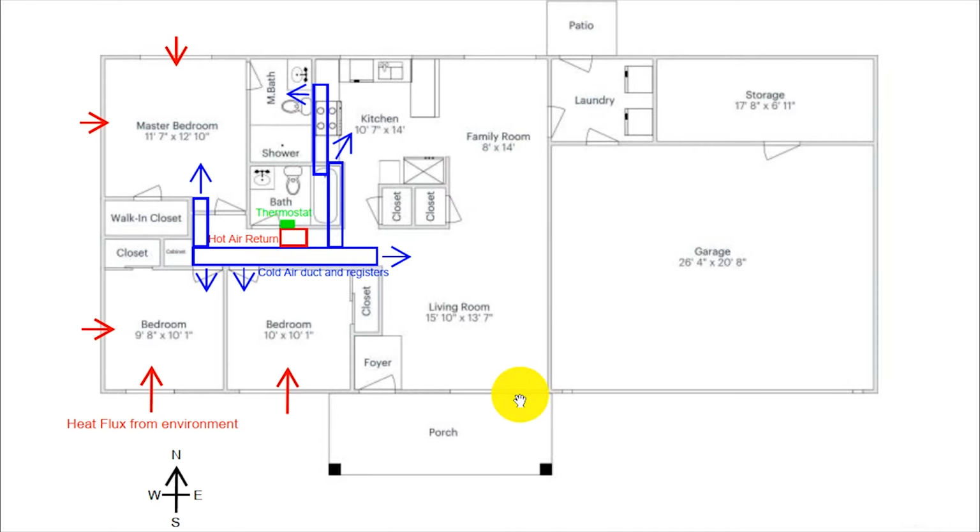So to fix this issue, I decided to install hot air returns in each of the 3 bedrooms. These would be installed in the ceilings, and I settled on 10-inch by 10-inch returns for each bedroom. 10 by 10 is the smallest size return register I could find that could fit a standard air filter. I estimated it big enough because the main air return in the hall here is a 25 by 20, and 3 10 by 10s represents an increase of 60% in filter area for that return.